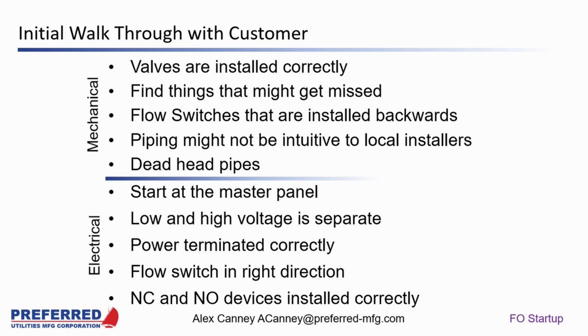I would start at the control panel, especially the master panel if it's a multiple panel system. And I would look to make sure that you have your low voltage and your AC wiring separate, so that there's no noise created. Making sure that the low voltage wiring is not run in the same conduit with AC, that's a big no-no. Making sure that the power is terminated properly. Making sure that you don't see any bad terminations for wiring, and first off, making a quick glance across a terminal of, like, say, an FSC or even a terminal strip in a PLC type panel. If you look at the wiring diagram, you can pretty much spot pretty quickly if you got wires landed in the right places.